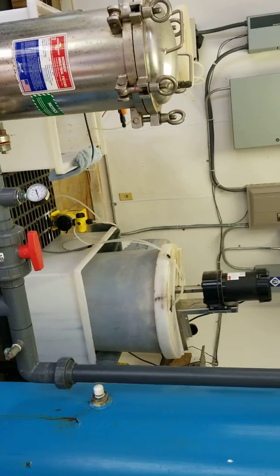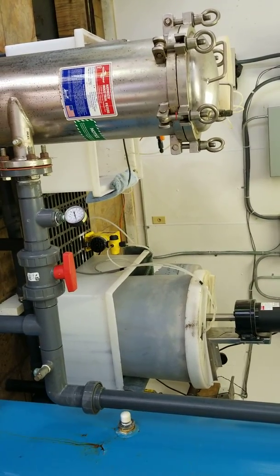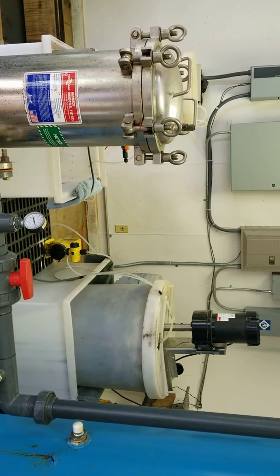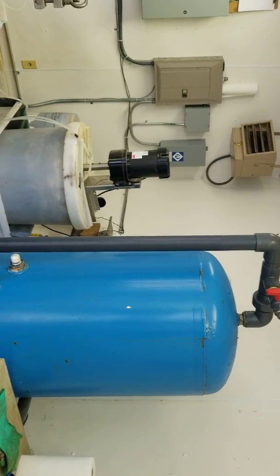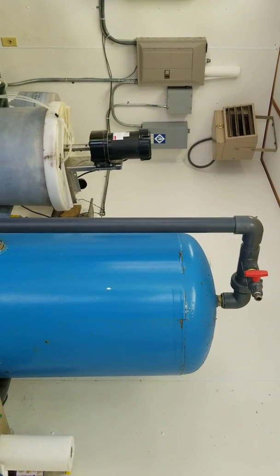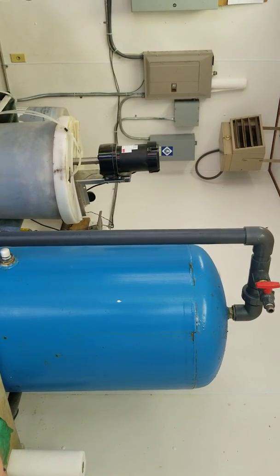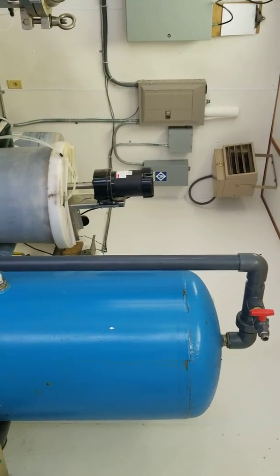I don't know what kind of questions you got. John was supposed to be here, and I was going to ask him a couple things. We've got some repairs that we need to make here in the pump house, and he was aware of that. That floor's settling a little bit over there by the hatch, and what actually caused that was we used to have 2 of these detention tanks. One used to sit right over on that corner, and that's a lot of water and a lot of weight, and it caused that floor to settle over there. John did get Jimmy up here, and we stabilized it with a post down underneath quite some time ago, but he hadn't been back to actually level out the floor yet. So that's one of the repairs that need to be made here.